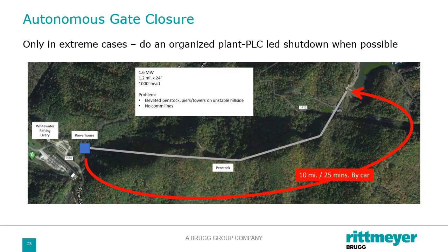But here's an example where we're looking at an autonomous gate closure. In this case, it's about a 2-kilometer penstock, but to get there by truck, it's a good 25 minutes or more drive. So you don't have time to go inspect something and find out why there's an alarm or what's happening if there's a loss of communication. In this location, they don't have good comlink alternatives, so what they're having to do is put in a radio link with a repeater. That repeater is unfortunately having to be mounted fairly close to the penstock. This is that site where I said over the last 10 or 20 years, this hillside has gotten to be unstable. So they're very concerned about a rock slide taking out this above ground penstock.